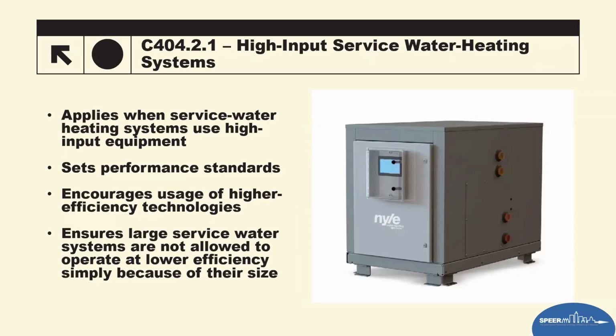High input service water heating systems. This one basically services those large capacity water heaters. So for large multifamily that's all tied together, hospitality, other things like that, rather than using standard performance values in C404.2, these larger systems basically will meet more stringent criteria and use advanced technologies. So the idea here is to avoid a situation where scaling up the load means accepting lower efficiencies. For designers and specifiers, if your hot water plant input is high beyond typical domestic scale, you need to check section C404.2.1 for specific compliance paths.